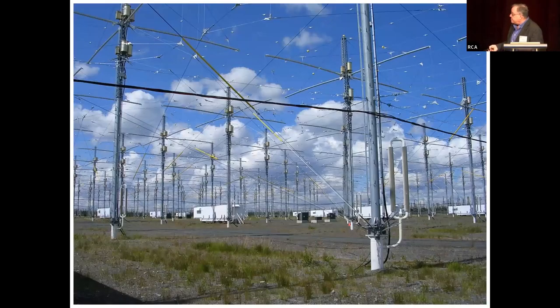Here's a view of the HAARP site. There's the thermosiphon with radiators — in summertime it does nothing, but in wintertime it's easily 30 to 40 below, often 50 to 60 below in this part of Alaska. Coming up the tower there's local area network fibers and fire alarm stuff. You can see the ground screen — a 15-inch square of alumi-weld wires grounded to the towers' excellent ground plane, like a flat sheet of metal for HF. You can see the low-band dipoles, east, west, north, south. The round cans are the matching units — fixed-tuned, with vacuum relays to release the half-dipoles when we don't want that band. There are six transmitters per shelter building — they're custom-built for our use.